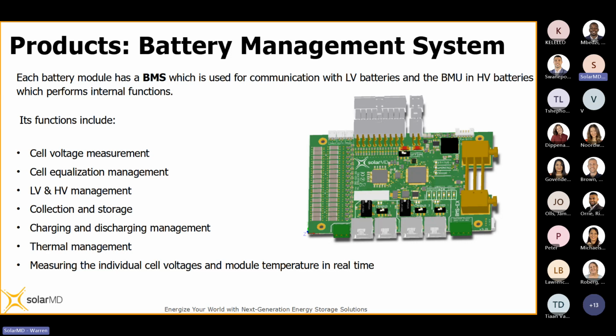What the BMS does is, with the aid of a shunt - that big brass lump of metal on the far right of the BMS image - measure how many amp hours have come and gone from the battery. The BMS knows the size of the cells. For example, in our older 7.4 kilowatt hour batteries, the cell size is 144 amp hours. So if the BMS sees that 140 amp hours have gone out of the battery, it knows the battery is basically depleted.